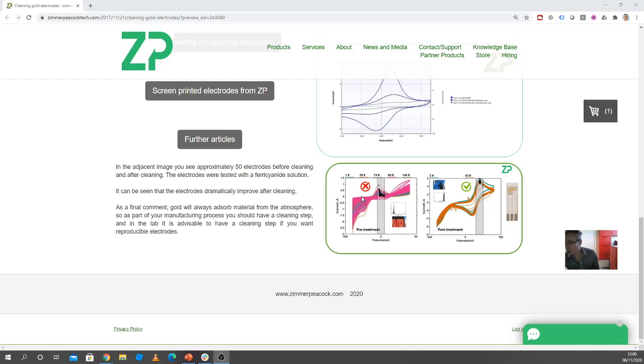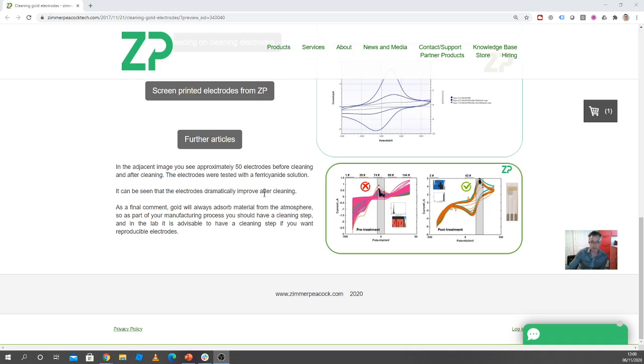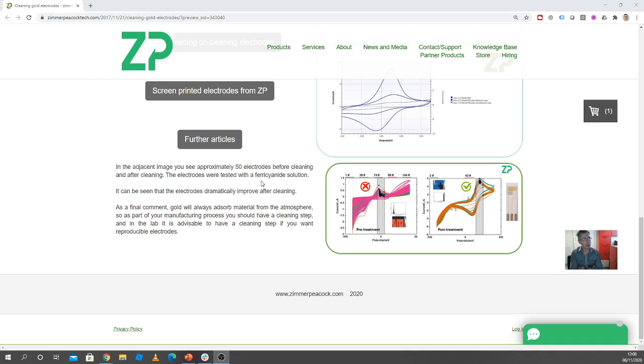Now when you manufacture a gold electrode, it's fairly pristine at that point, and then with time gold is really good at absorbing materials from the atmosphere. So our advice is that if you're manufacturing with gold electrodes or even if you're doing R&D with gold electrodes, you do have to have a cleaning procedure in there. It's not because we're not making the gold electrodes well, but we're finding, and I think it's anecdotally known, that gold is quite good at absorbing molecules onto its surface.